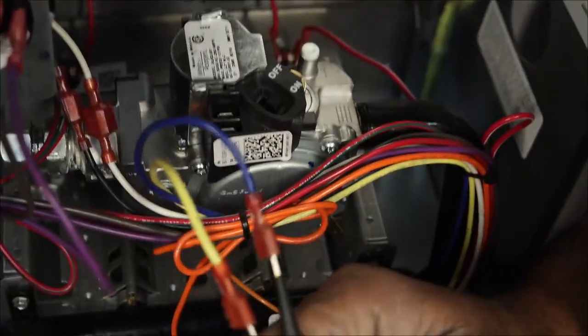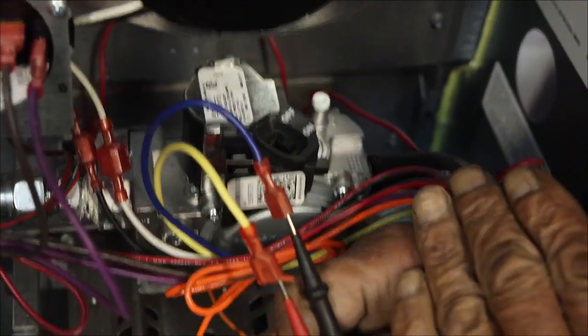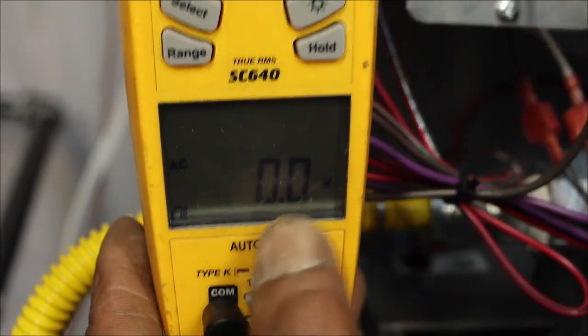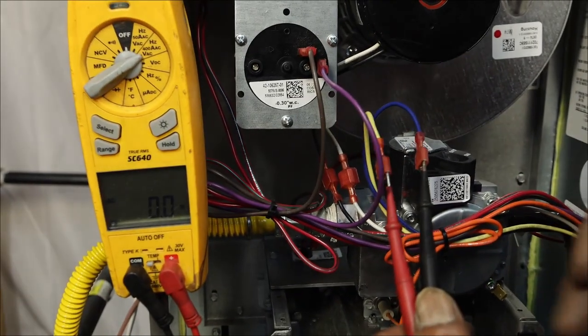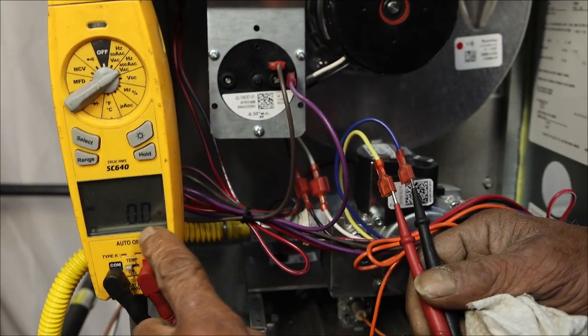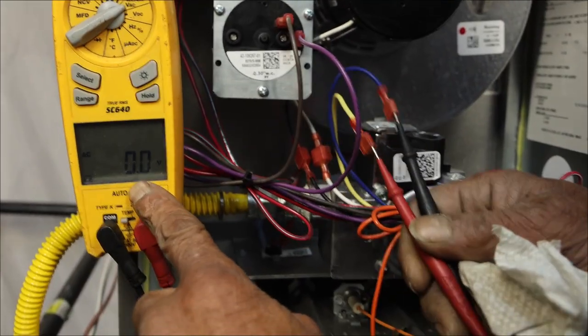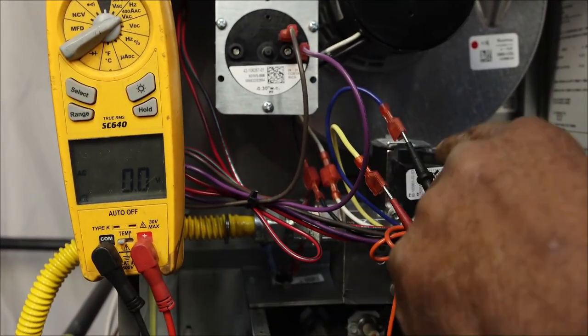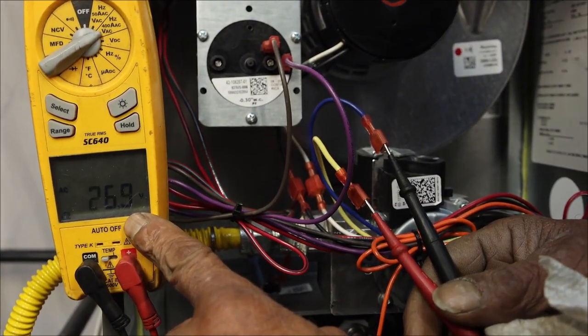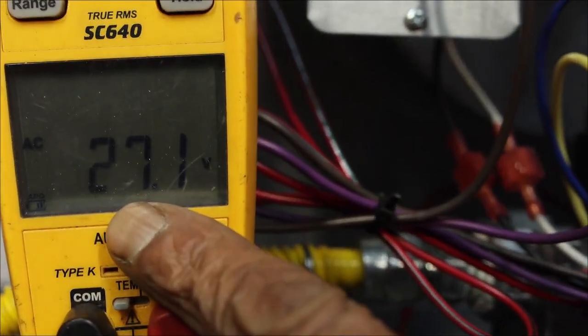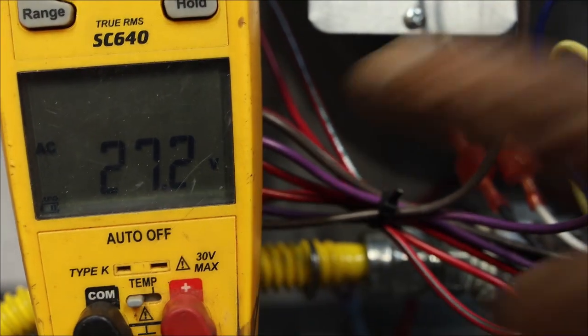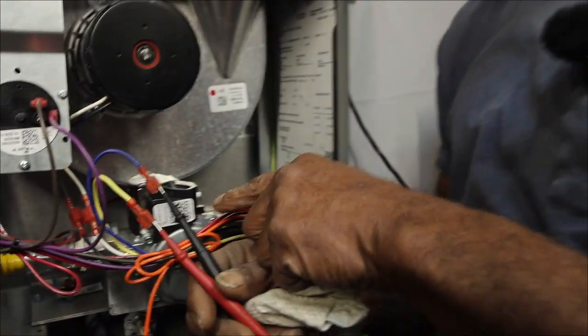We're going to turn it back on. Now, it's going to take a moment, and then the system will go back into its heat cycle. Now, if I watch my amp probe, when the glow plug, or on here, it's not a glow plug, it's a spark igniter. But when the spark igniter begins to flicker, you'll hear it, click, click, click. And at that point, when you look at the amp probe, you'll see 24 volts going to the gas valve in order to energize it. There's the 24 volts. Well, in this case, 27. Same difference. That sent power to my gas valve.